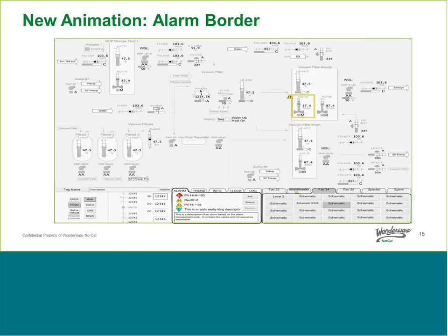You could drill down into that. But at the level 1 overview display, you want to provide limited use of color and animation, and only use color selectively when you need to alert the operator that they need to focus their attention. This alarm border is a capability and animation that's built into the graphics library now, and we'll show you that in an actual demo.